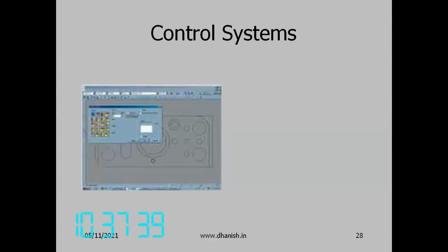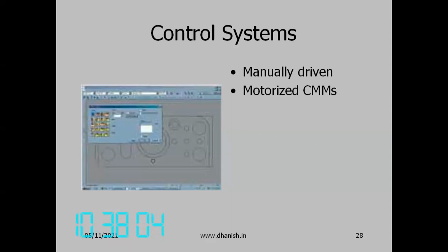Next we come to control systems. Control systems control the movement of the probe around the workpiece surface. Different types of systems are there. We have the manually driven systems, the cheapest. Then motorized CMMs, where you press a button and a motor drives the CMM. But when it reaches the workpiece, you have to stop and move slowly till it contacts the workpiece. That is the motorized CMM. And direct computer control: you give commands to the computer, and the computer coordinates the motions. It goes at a fast speed till near the surface, then moves slowly over the last distance to contact, and the data is captured.